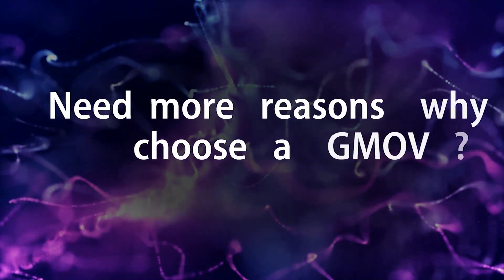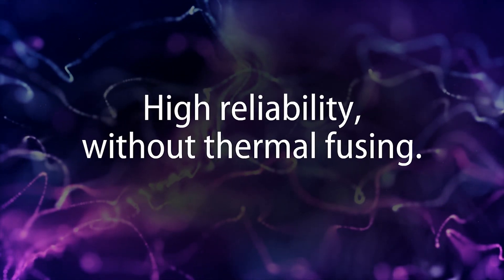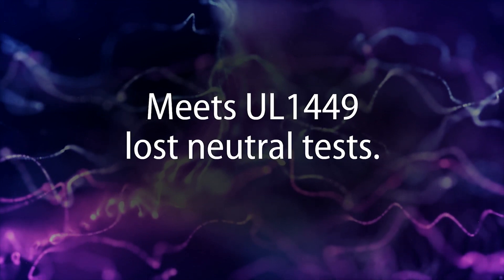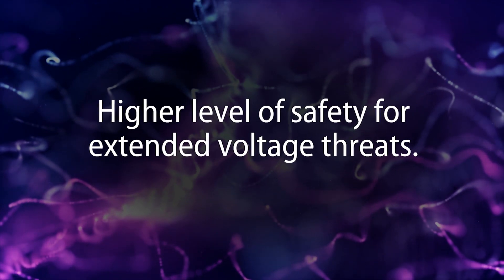Need more reasons why GMOV is an optimal protection solution? GMOV improves application reliability without the need for thermal fusing. GMOVs effectively do away with the need for more costly and higher performance MOVs to meet UL1449 lost neutral tests. It also provides a predictable failure mode, thereby removing the need for indication circuitry and associated costs. And importantly, GMOVs offer a higher level of safety compared to MOVs alone for extended voltage threats.